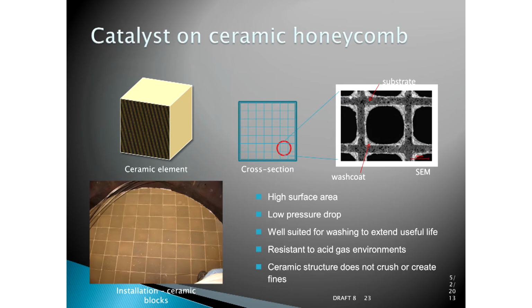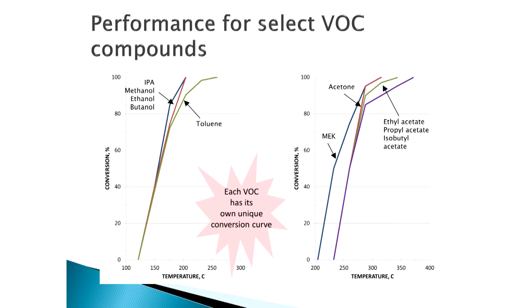And going back to what we talked about before, every VOC has its own unique profile across the catalyst. So some compounds like methanol and ethanol will ignite at relatively low temperatures. Other compounds have to go at much higher temperatures. So be it thermal or catalytic, we need to understand what these profiles are. And if you're dealing with a situation like in a gas-fired power plant, you're inside a boiler where you have a very fixed temperature, you have to understand what these profiles are so that you can design whether VOCs can be destroyed in that application or not. So it's very, very critical. Each VOC has its own unique conversion curve.